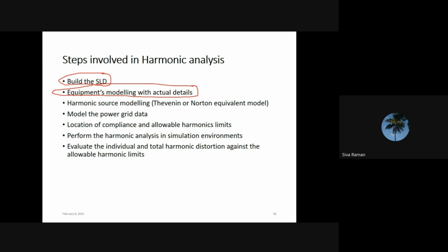The first one is building the single line diagram. First we have to model the single line diagram as per the actual plant. Even in the plant planning or design stage, we should have a plant layout and a tentative single line diagram, and based on that we build the single line diagram in the simulation software. The second one is equipment modeling with actual values. Equipment modeling involves the solar inverters, inverter duty transformer, cables, transmission lines, transformers, and capacitor banks or reactors, etc.